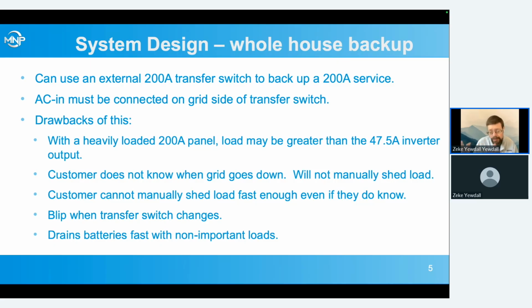So if you've got a critical or backed up loads panel, try not to call it a critical loads panel, because that is something completely different in the code, and trust me, you do not want to be subject to those code requirements. So we try to use the term backed up loads panel instead. If you've got a backed up loads panel, you can get rid of those big loads. But when the customer has the whole house backed up, they don't know that the grid even went off to know to turn off those loads.